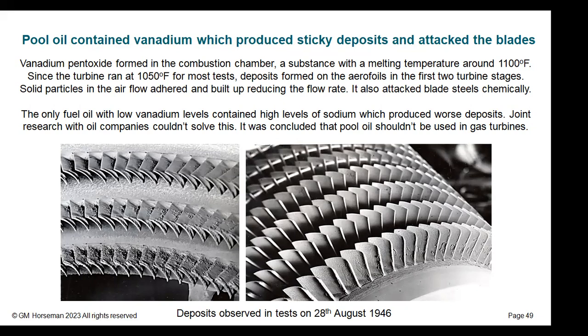Any ash that passed through adhered to the gummy substance and started to block the blades up. So in some of these photographs, the deposits you see are often after only 40, 50, maybe as much as 150 hours, but not usually much more than that — very short periods compared with a power station application, where you'd normally expect thousands of hours.